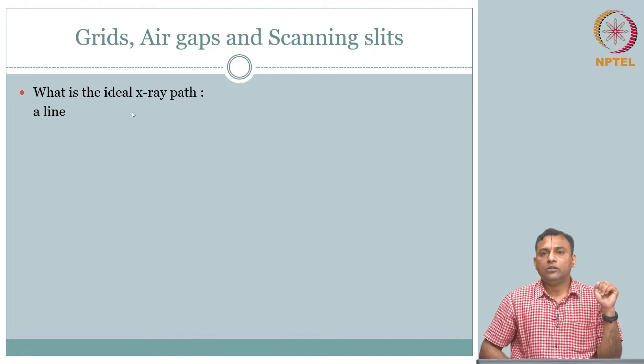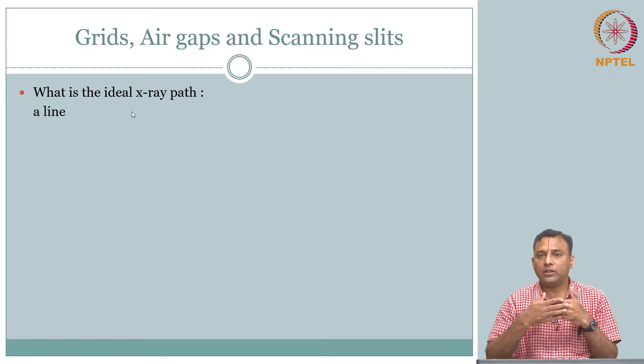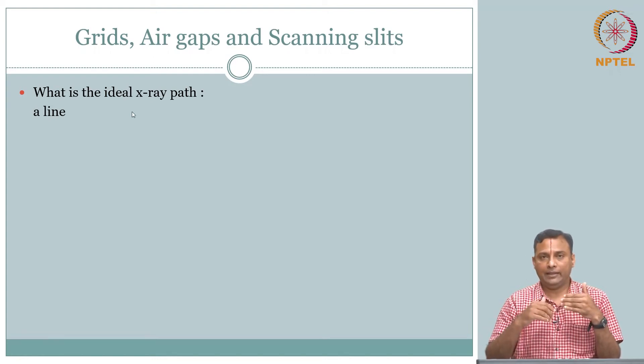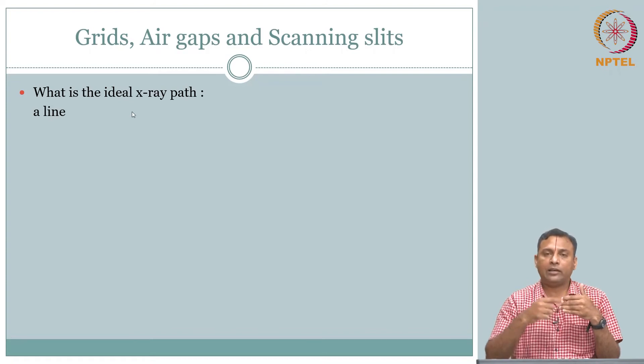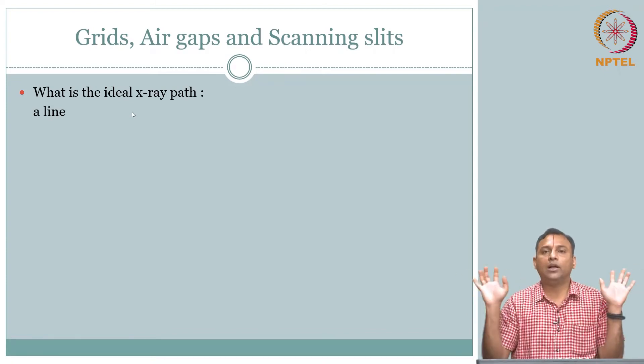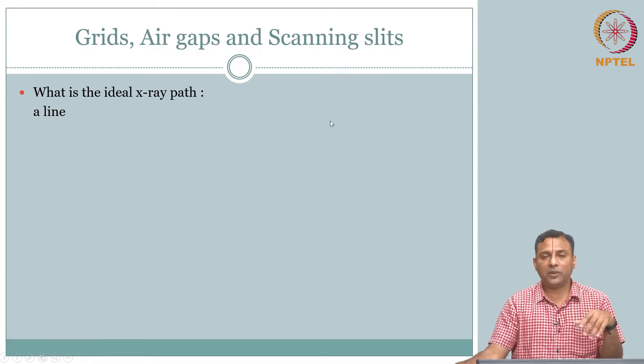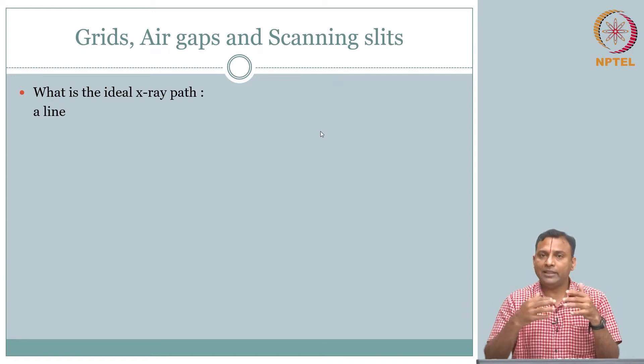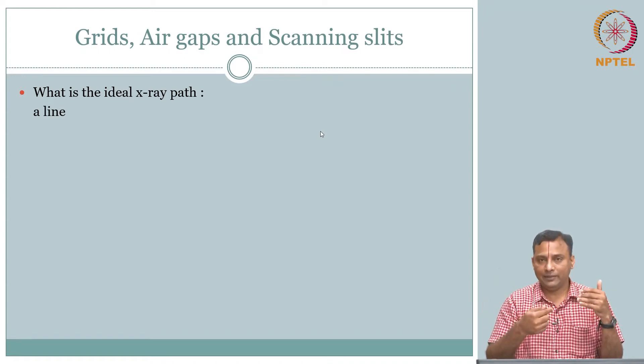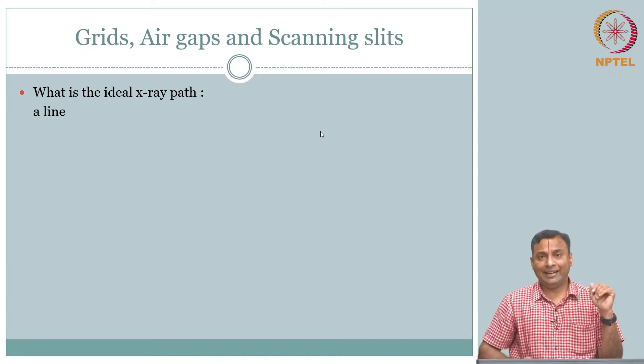What is the ideal path? We have the x-ray source sending out a cone — it diverges, but it is always travelling along a line. If I have a detector, I expect the photon to come out along the same line — that is my signal along the path. Ideally I want only the straight-line path, so that if a photon hits my detector, I can say it came through the line connecting the detector point to the source point. That is the ideal signal. So grids, air gaps, and scanning slits all have the objective of minimizing scattered photons while maximizing photons entering through the straight-line path.